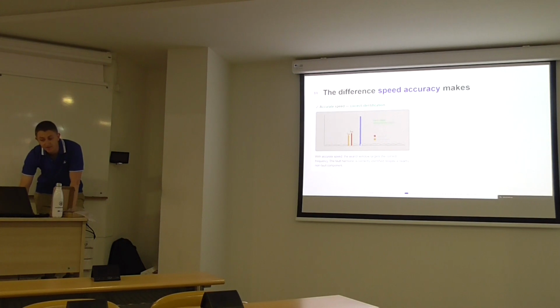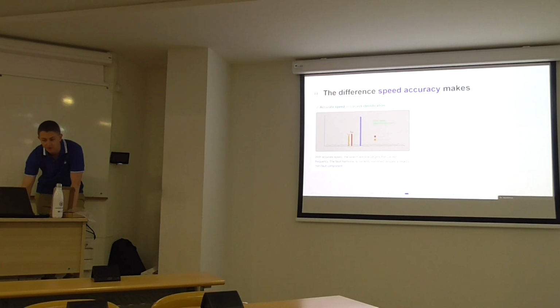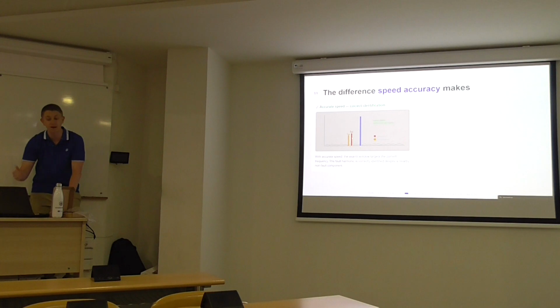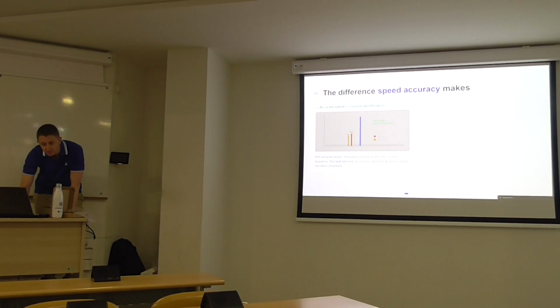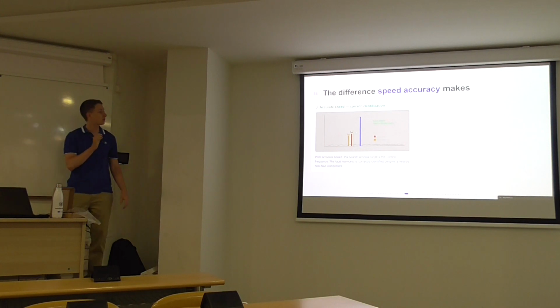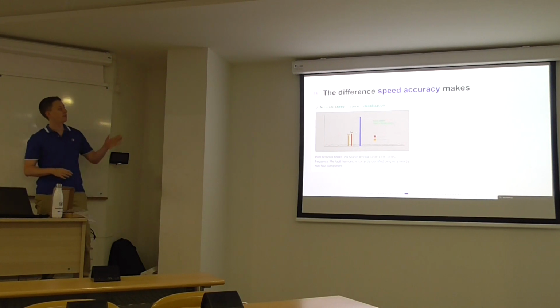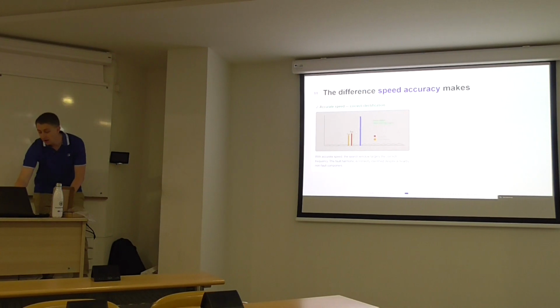We have the fundamental component, the highest peak in the spectrum. And then we have two harmonics. One is a fault harmonic, it can be, for example, a broken bar harmonic, and another one that's not related to a fault. It can be caused, for example, by load oscillations. So if we have an accurate speed, the search window here targets the correct frequency. So the fault frequency is correctly identified despite a nearby non-fault component.